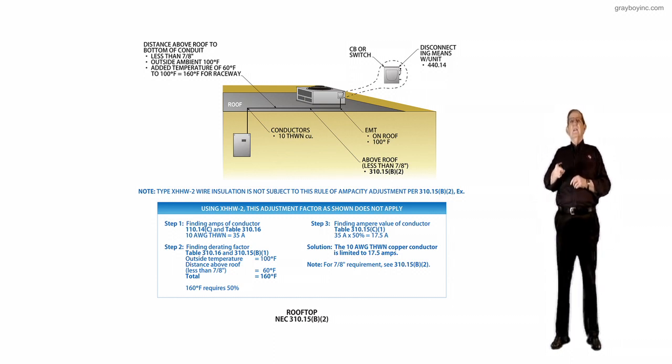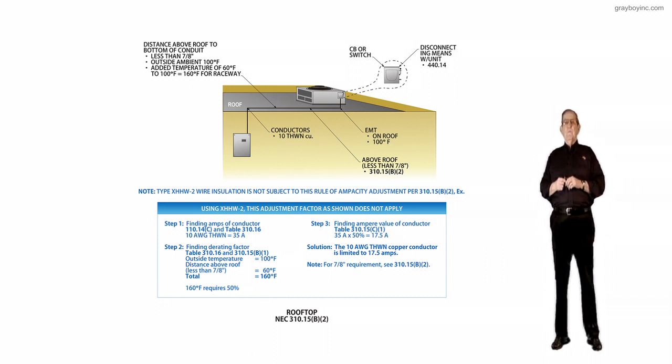Now let's look at it where you're less than 7 eighths of an inch from where the conduit sits on the roof. Step one, you go to table 110.14C, table 310.16, and a number 10 THWN is 35 amp out there in a wet location. That's considered by 300.9B a wet location.